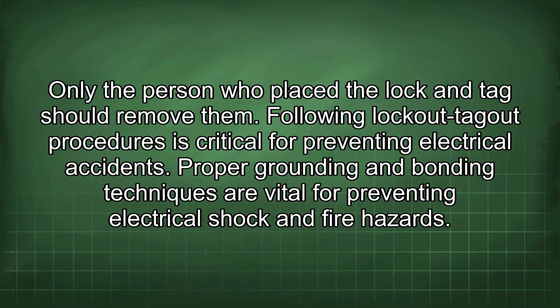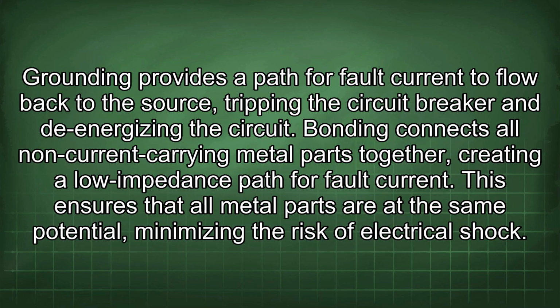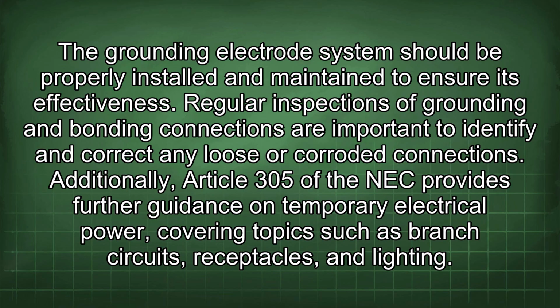Proper grounding and bonding techniques are vital for preventing electrical shock and fire hazards. Grounding provides a path for fault current to flow back to the source, tripping the circuit breaker and de-energizing the circuit. Bonding connects all non-current carrying metal parts together, creating a low impedance path for fault current. This ensures that all metal parts are at the same potential, minimizing the risk of electrical shock. The grounding electrode system should be properly installed and maintained to ensure its effectiveness. Regular inspections of grounding and bonding connections are important to identify and correct any loose or corroded connections.